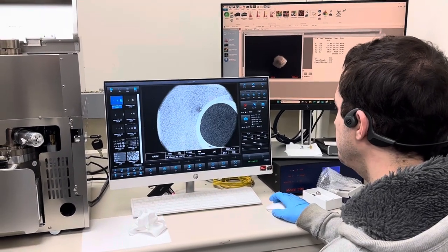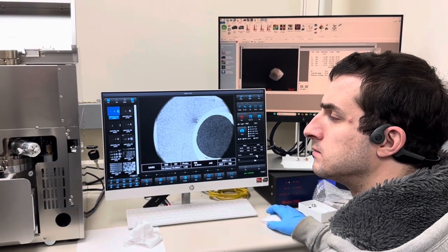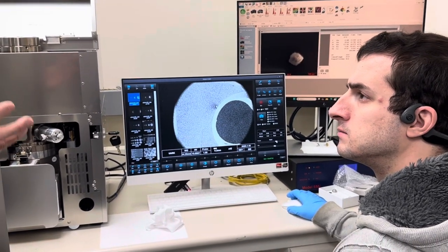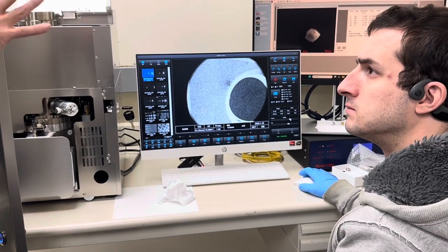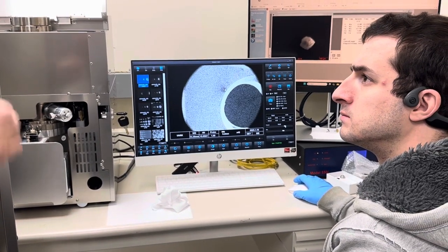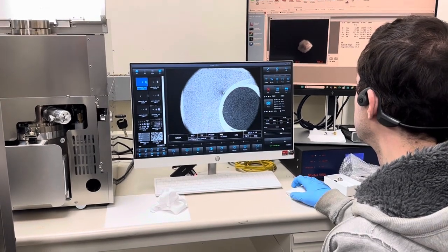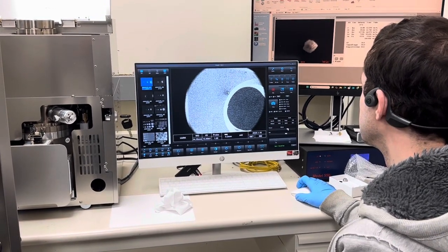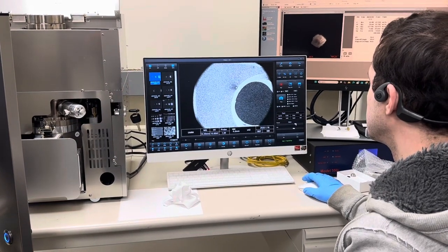Yeah. So now you're electromagnetically moving the beam around to where we're saying we're kind of close to saturation. Not really sure. But now after I've maximized all of that, I'm going to run it up just a little bit up my curve. So I'm going to go to 750, just to give it a little bit more juice. And now I'm going to play with my gun sliders again.